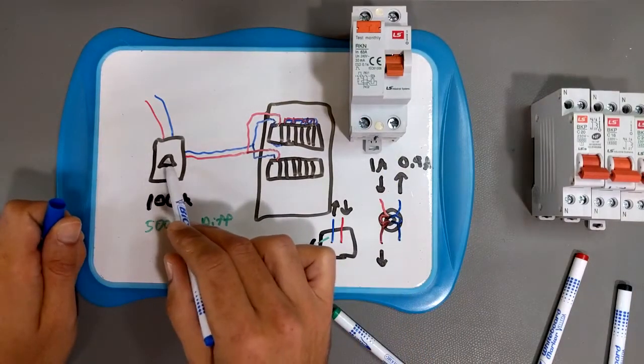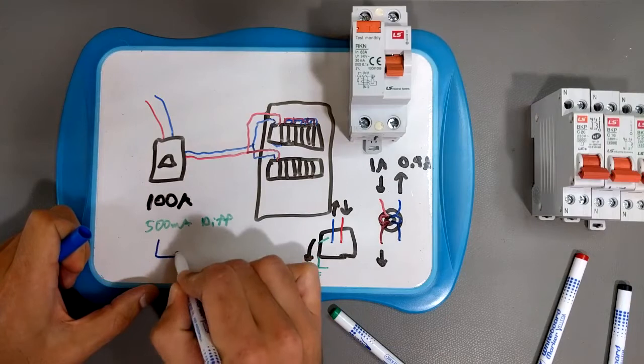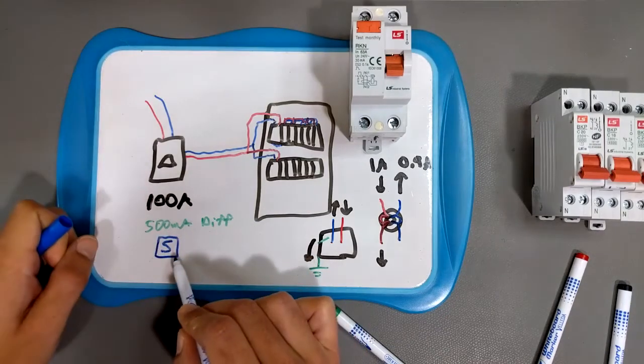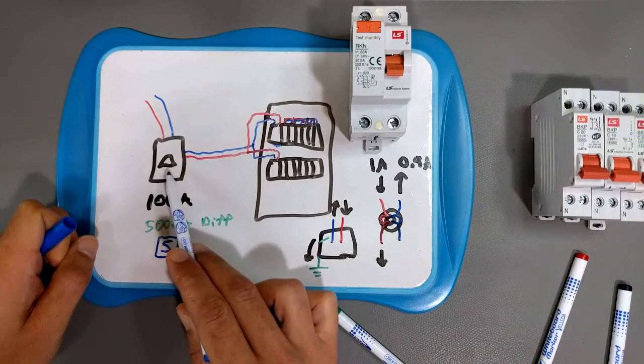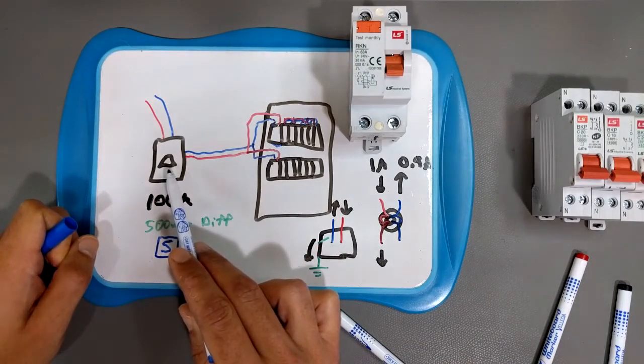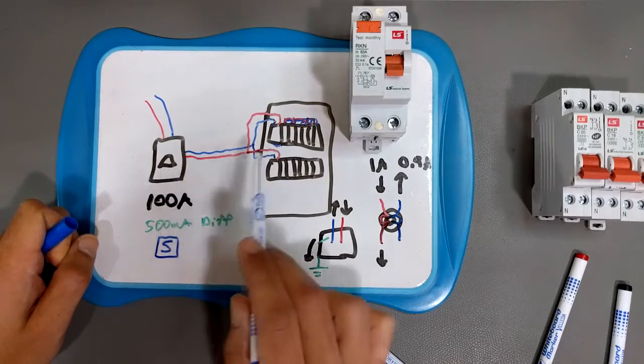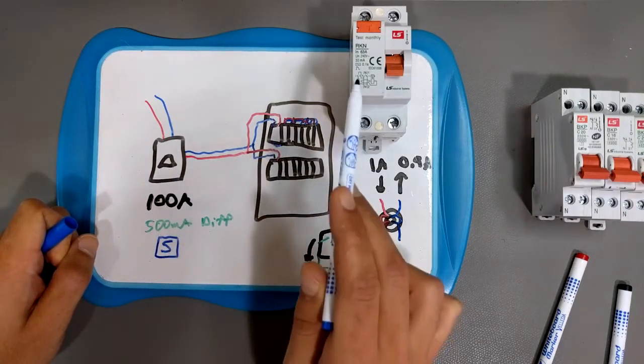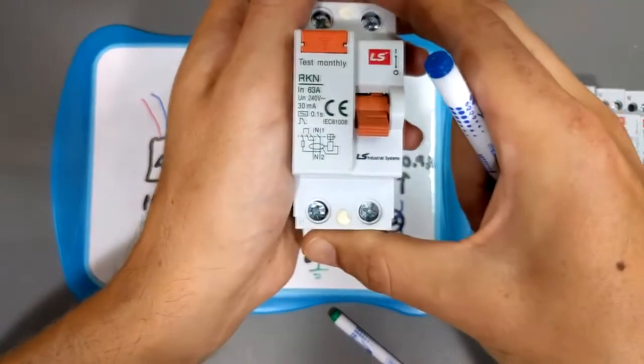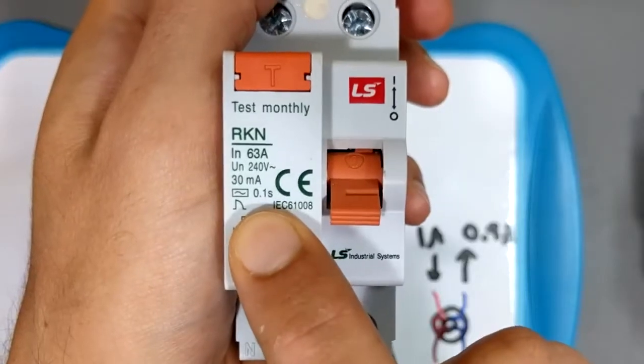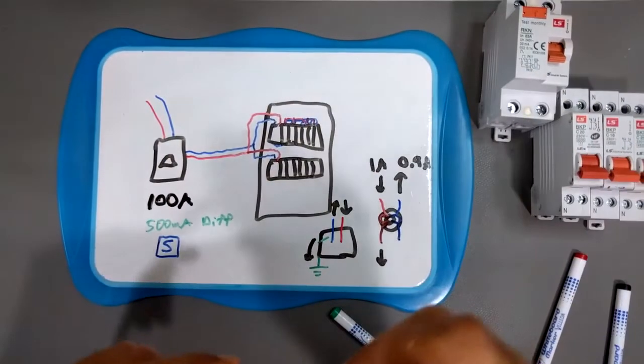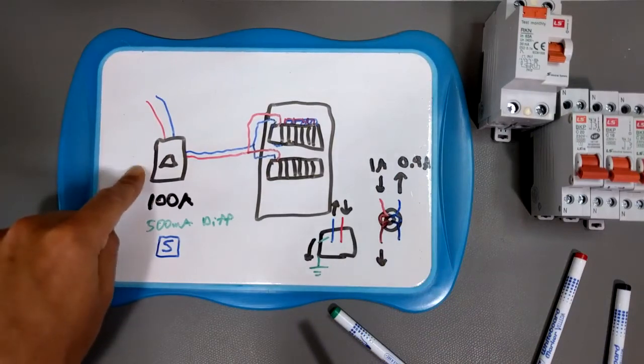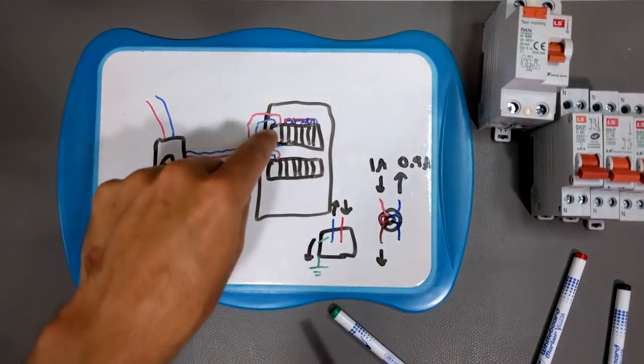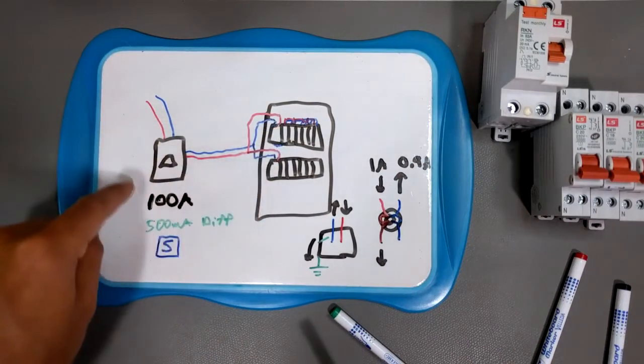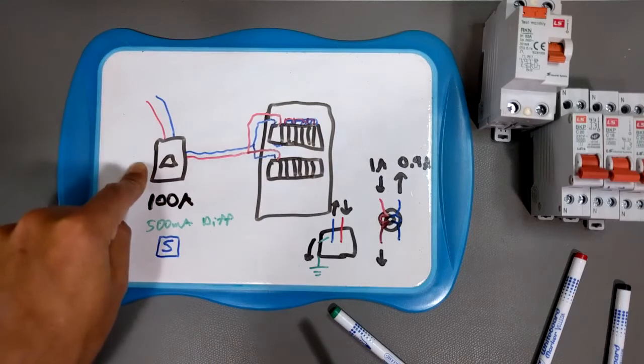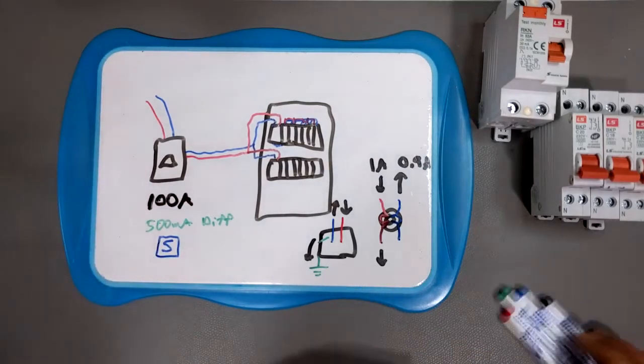Well, what they do is, this is usually a selective. Usually on the box, at least where I live, they put an S on it, and that means it's selective. And all that means is that this guy is going to trip in something like 200 milliseconds, whereas this guy, also a differential breaker, is going to trip in, as it says written on here, you can maybe see that there, 0.1 seconds, 100 milliseconds. So the whole idea here is that this guy has a delayed trip. So that allows the differential breakers here to trip first, and then second, this guy will trip. That's just a little technical detail.